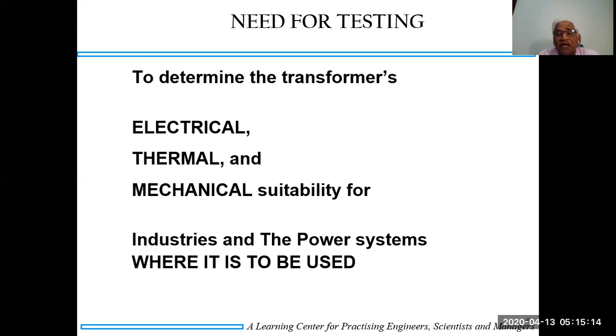That is important. Mechanical: whenever there is a short circuit outside the transformer, the transformer has to supply the short circuit current. So there is a lot of stress on the transformer windings inside. The winding should not give way and damage the transformer.